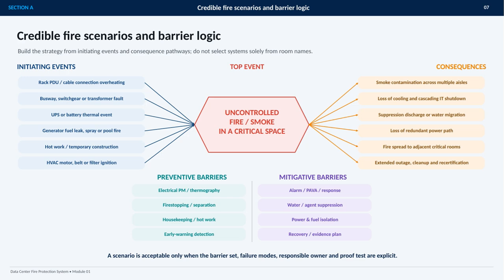The strategy therefore combines preventive barriers, such as electrical maintenance, thermography, separation, housekeeping, hot work controls, and early detection, with mitigative barriers, including alarms, response procedures, suppression, power and fuel isolation, and recovery planning. A scenario is acceptable only when its barriers, failure modes, responsible owner, and proof test are explicit.